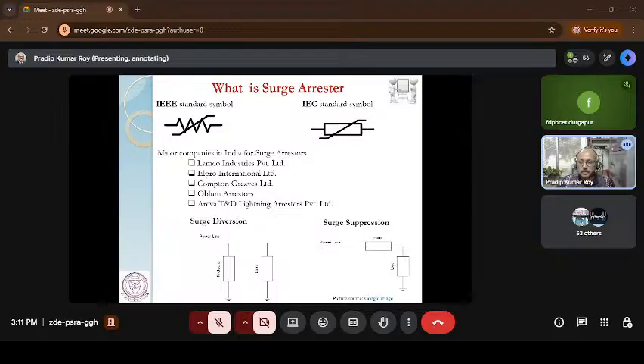So when I talk about this in terms of protection level, you can look at this graph. The first graph shows that the load is basically the transformer and the protector is basically the surge arrestor. The transformer and surge arrestor are installed in parallel, connected to the high voltage, and both are grounded. In normal operating voltage, the surge arrestor acts as an insulator. There's no current flowing through the surge arrestor. So if any current is going from the transformer to the household part, there is normally no leakage through the surge arrestor.